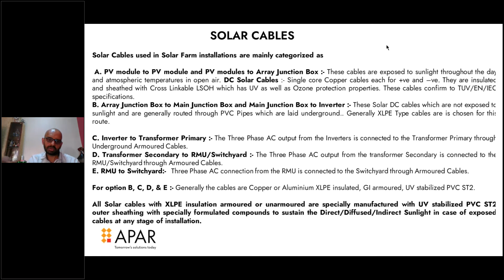Now, category A is always copper cable, or tinned copper cable with XLPO insulation. As for categories B, C, D and E, which are the array junction, inverter to transformer, and RMU to switchyard, it could be copper as well as aluminium. We actually promote aluminium because the cost difference is quite high. Today, copper is at an LME of 10,000, whereas aluminium is only in the range of 2,500. And since these are underground cables, we suggest that going aluminium is a better option because you get the same characteristics of the cable as copper. You just have to go one size higher.